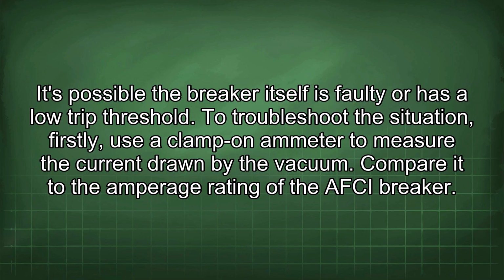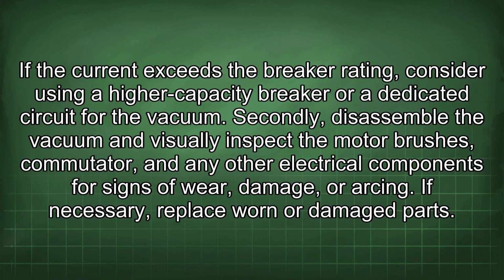To troubleshoot the situation, firstly, use a clamp-on ammeter to measure the current drawn by the vacuum. Compare it to the amperage rating of the AFCI breaker. If the current exceeds the breaker rating, consider using a higher capacity breaker or a dedicated circuit for the vacuum. Secondly, disassemble the vacuum and visually inspect the motor brushes, commutator, and any other electrical components for signs of wear, damage, or arcing. If necessary, replace worn or damaged parts.